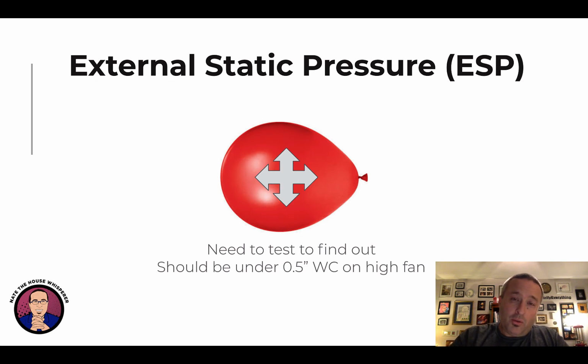So you need to test this. Going forward I'll use ESP, abbreviated for external static pressure, since it doesn't fit on the slides well. You need to test to see what this is—it should be under 1/2 inch when on high fan.